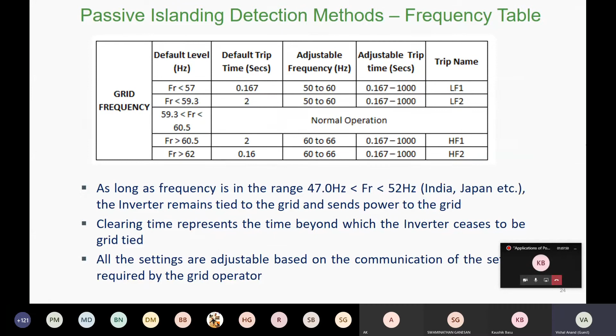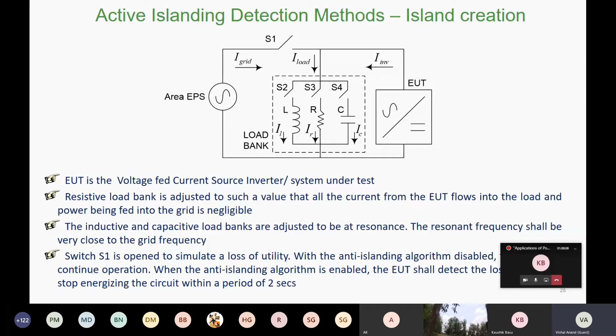Finally, we also have active islanding methods, where the voltage and frequency might be within the acceptable ranges. In such a case, the grid tie inverter must be able to detect the island formation using some active islanding method and disconnect. We use reactive power perturbation, which is a simple technique. This has to happen within 2 seconds. For example, once every quarter second, or 250 milliseconds, we keep perturbing the reactive current, look for variations in the frequency, and disconnect. So this is the brief presentation that I had. Now we'll continue the discussion in the remaining talk, and I hand it back over to you, Kaushik.